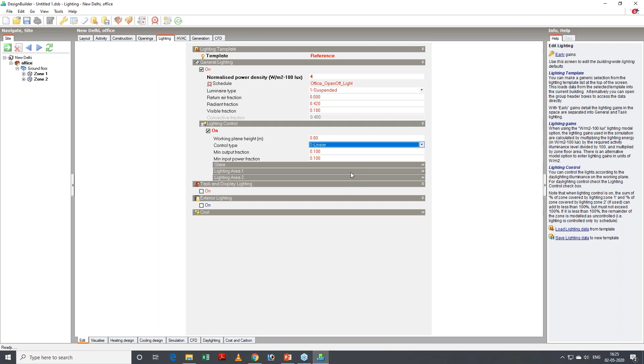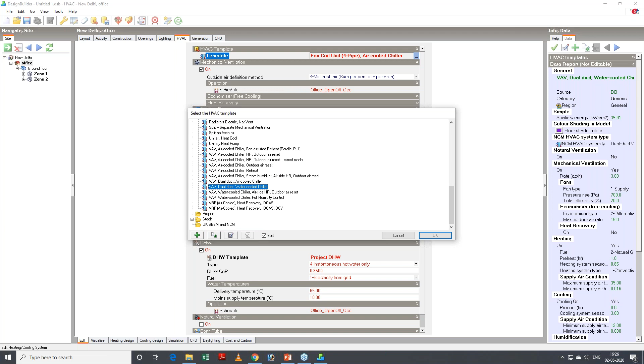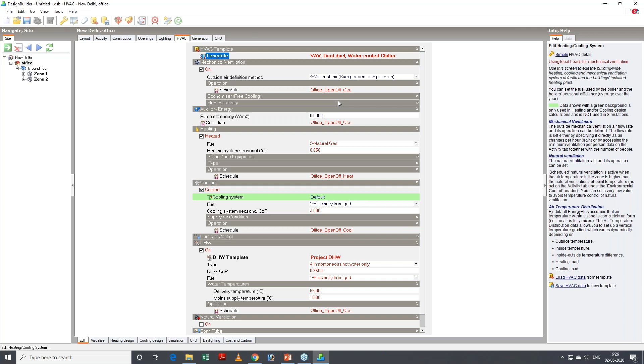Then comes the HVAC. You can refer to NBC for the type of HVAC that can be used in your building. In NBC, it says for office building, if the area is more than 10,000 square meter, then you have to use the variable air volume chilled system. So I'm using that in this schedule. Again, the schedule you can set for when your AC will start and when it will close. Accordingly, you can copy the schedule and make the schedule according to you.